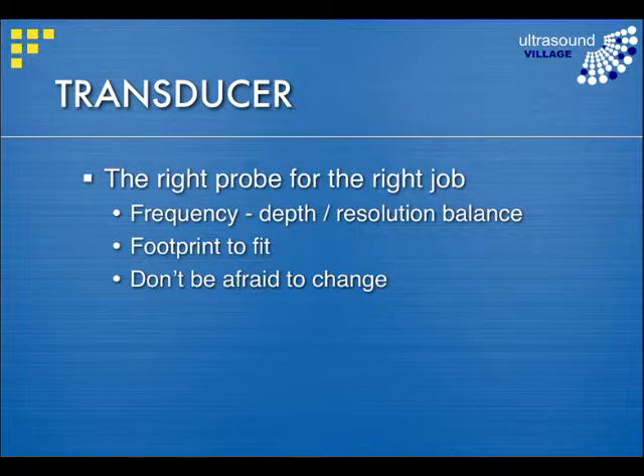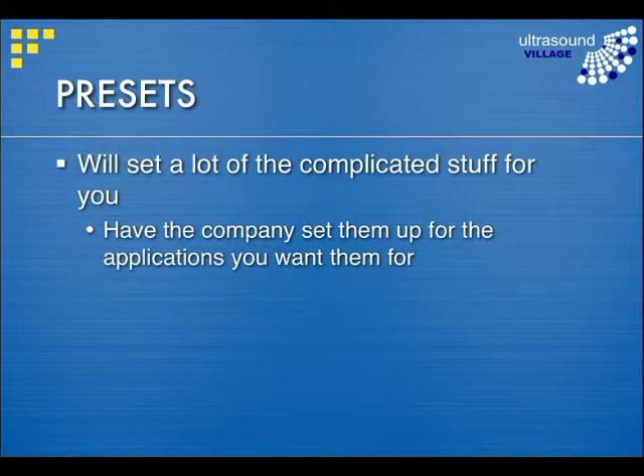Many transducers these days are multi-frequency and on some machines you can select the frequency at its lower or upper range. Don't be afraid to change this during the scan. Presets are very useful and the company and sonographers will help you set these up to optimise the images you get. This deals with a lot of the post-processing algorithms the machines incorporate. For most people who are occasional users, it's much easier to just select the appropriate preset.